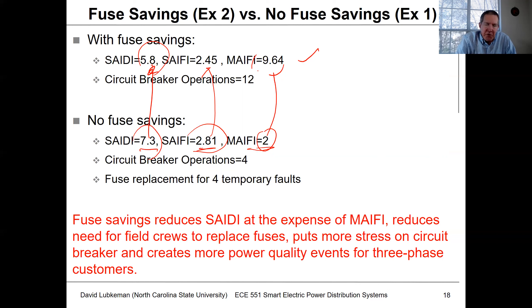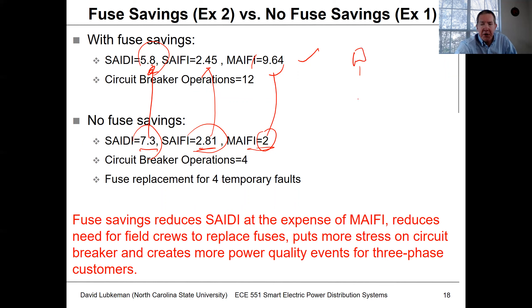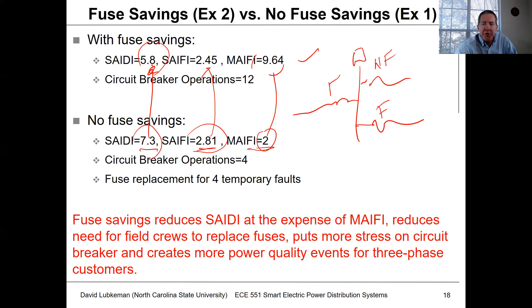Fuse savings is beneficial in that it cuts down on SAIDI, improves SAIFI somewhat, and means fewer truck rolls to the field. However, if there are power quality sensitive customers — such as industrial customers where a blink could disrupt a process just like a sustained outage — this matters. As a reliability engineer you'd look at these trade-offs: knowing where customers are and what types of events they're sensitive to, you figure out which sections of the circuit have fuse savings and which don't. You can actually have a hybrid approach where some sections have fuse savings and others don't.